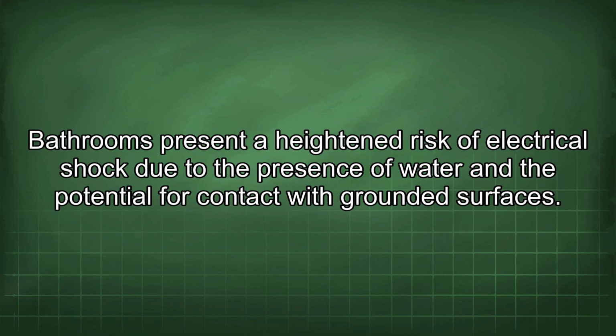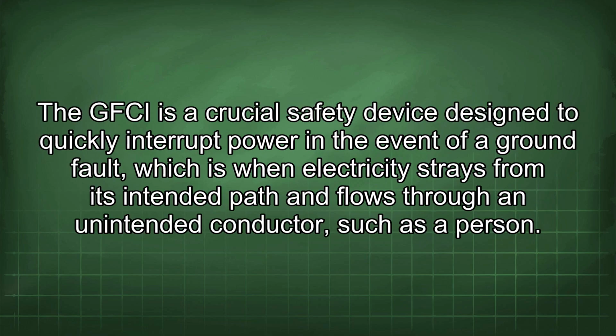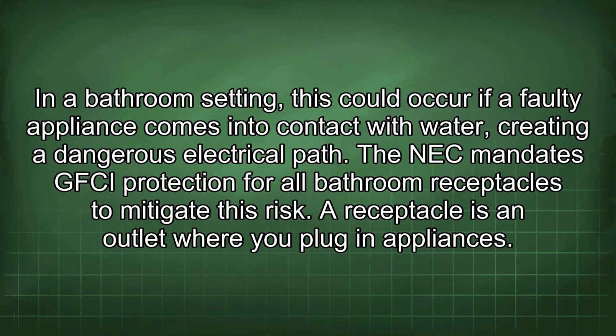Bathrooms present a heightened risk of electrical shock due to the presence of water and the potential for contact with grounded surfaces. The GFCI is a crucial safety device designed to quickly interrupt power in the event of a ground fault, which is when electricity strays from its intended path and flows through an unintended conductor, such as a person. In a bathroom setting, this could occur if a faulty appliance comes into contact with water, creating a dangerous electrical path. The NEC mandates GFCI protection for all bathroom receptacles to mitigate this risk.